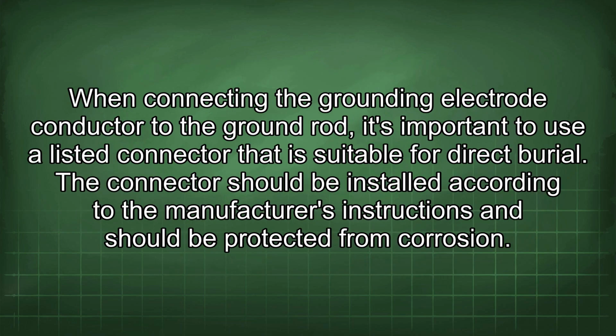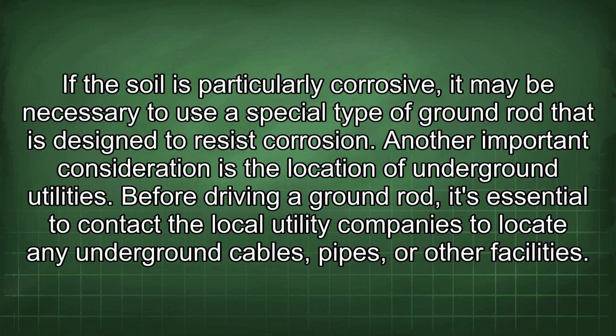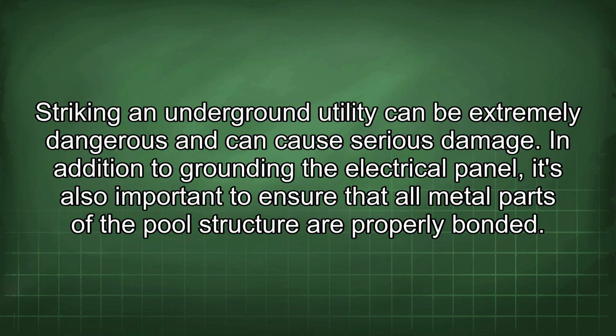When connecting the grounding electrode conductor to the ground rod, it's important to use a listed connector that is suitable for direct burial. The connector should be installed according to the manufacturer's instructions and should be protected from corrosion. If the soil is particularly corrosive, it may be necessary to use a special type of ground rod that is designed to resist corrosion. Another important consideration is the location of underground utilities. Before driving a ground rod, it's essential to contact the local utility companies to locate any underground cables, pipes, or other facilities. Striking an underground utility can be extremely dangerous and can cause serious damage.